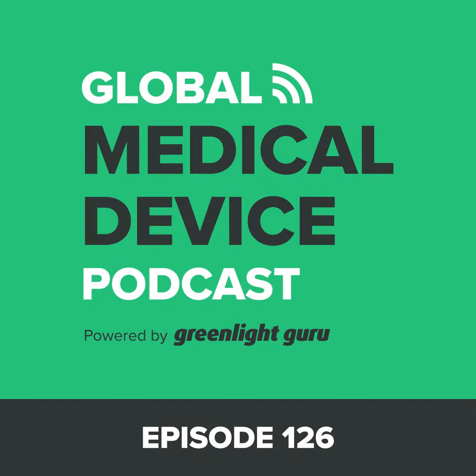But again, I want to focus on the quality failure here. So just to sort of lead the witness, John, from a supplier quality perspective, we are, quote unquote, required to identify second sources for vendors for critical suppliers. And most people would consider that if you have an ETO sterilized device, your ETO vendor will be a critical supplier. Do most companies qualify other companies in advance? And take that a step further, John. Does that second source need to be the same ETO provider? In other words, if you have a device that's being sterilized via ETO with one particular vendor, is it sufficient to identify a second source who also uses ETO? The vast majority of companies, in my experience, John, and you can either agree or disagree, do exactly that.